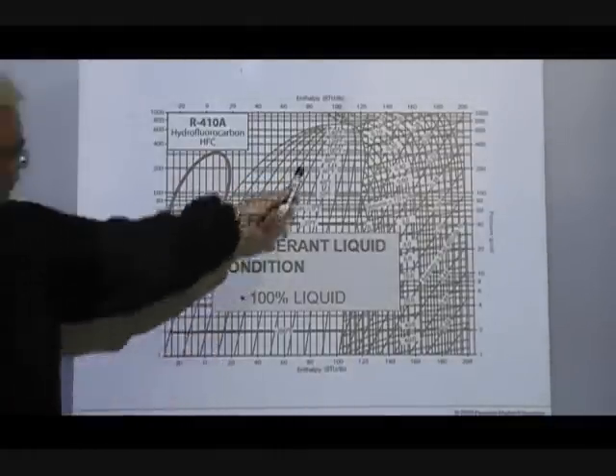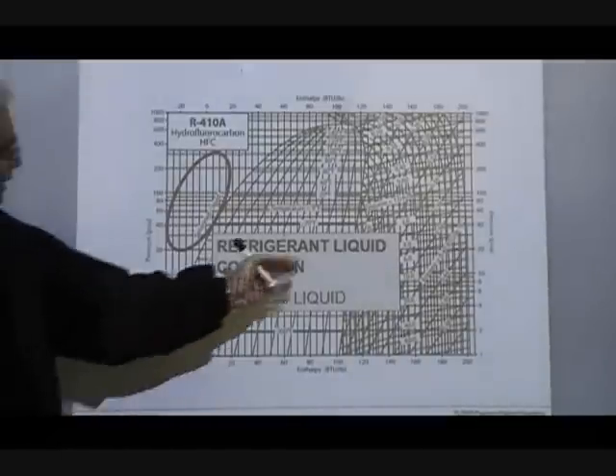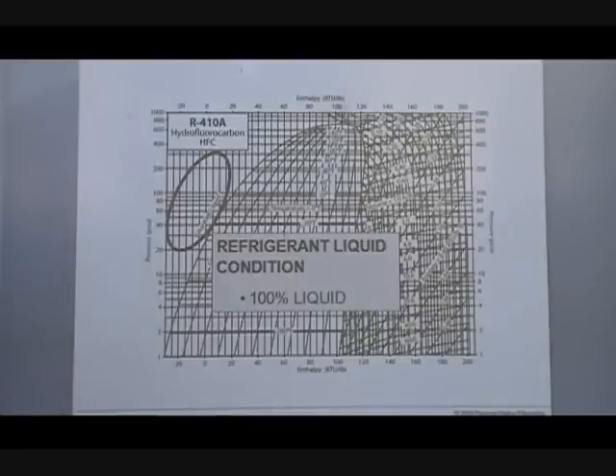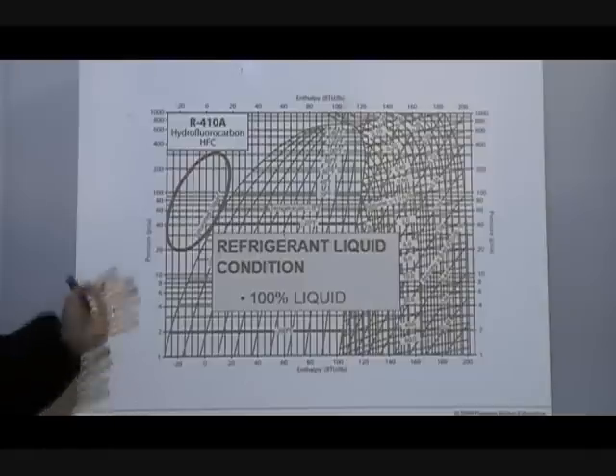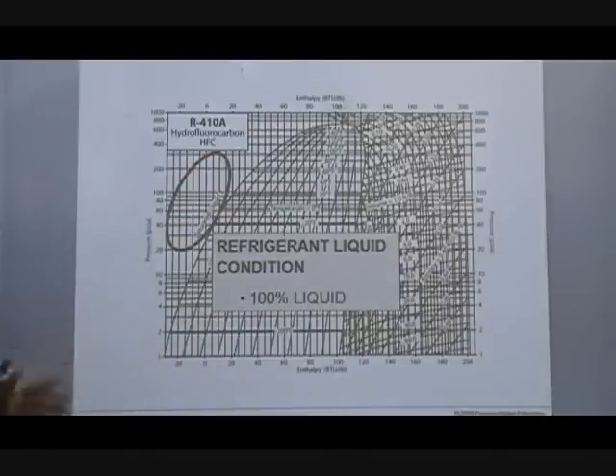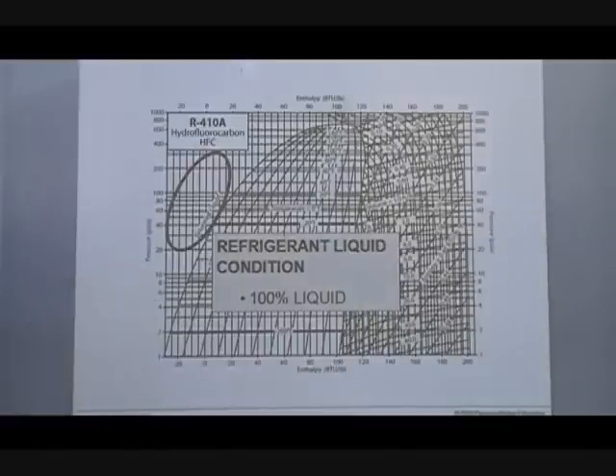These lines on the pressure-enthalpy chart are called lines of quality. Quality adds up to the saturated liquid, which is what you want — that's the best quality you can have. Why is it good quality? You've got to have 100 percent liquid entering your metering device. If you don't, it's like starting a drag race with your engine skipping and cutting out. So you need 100 percent liquid entering that metering device, and you can use the pressure-enthalpy chart to measure that.